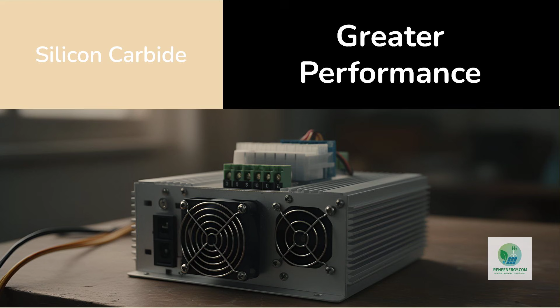Now consider hydrogen. Electrolyzers are fundamentally DC devices. They require precisely controlled current to split water efficiently. The electricity feeding them typically arrives as AC from the grid or renewable assets. Converting that AC into stable DC requires rectifiers and switching modules. Losses in that conversion process directly increase the cost of hydrogen.